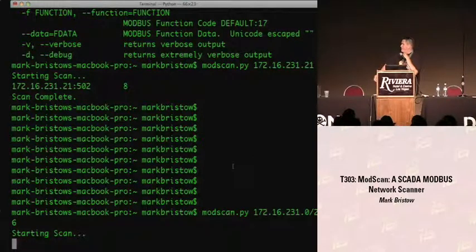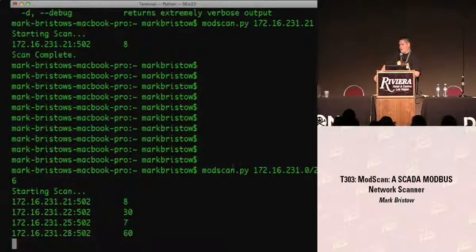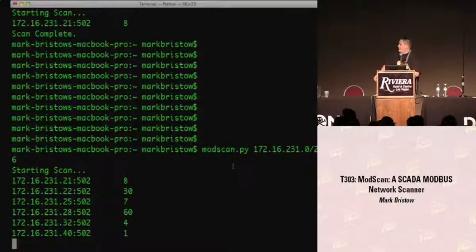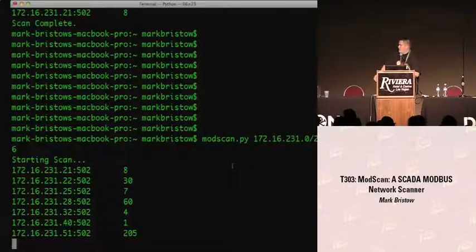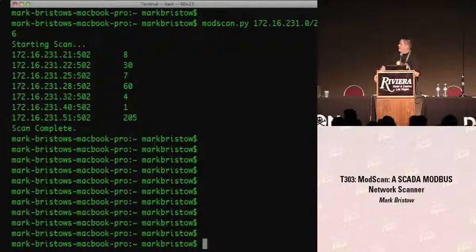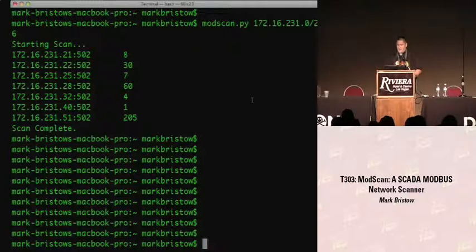This is going to take about 30 seconds to run. I'm doing a slash-26 because it takes on average about two minutes and nine seconds to do a whole class C, almost exactly every time. As you can see, we're getting some results: .21 has a slave ID of 8, .22 with slave ID 30, .25 slave ID 7, et cetera. Then it tells you when the scan is done. Pretty basic - it just sits there and scans the whole network and maps everything out for you.